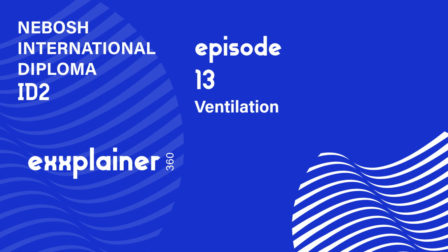Yeah. But structurally, they all share the same 5 essential parts. Okay, what are they? Let's break it down. First, you've got the hood. That's what collects the contaminant right at the source. Then, the ducts. The pipework that carries the dirty air away. Makes sense. Third, the air cleaner, the filter, basically. Got to clean the air before releasing it, usually. Okay. Fourth, the fan, the engine of the whole system, provides the airflow, the suction. The power. And finally, number 5, the discharge, the exit point, usually a stack where the cleaned air is released safely.